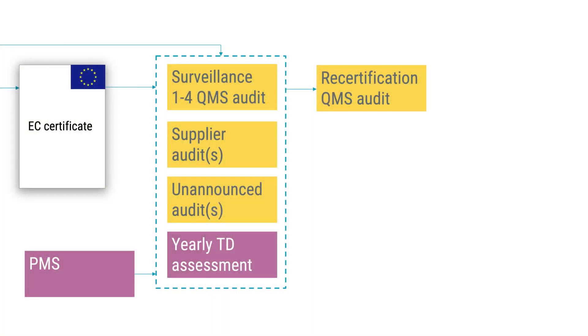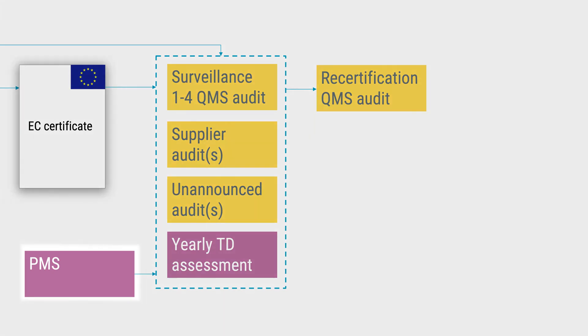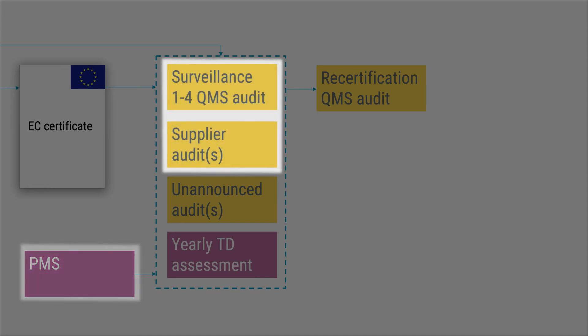When during the certification cycle the full range of the manufacturer's devices has been assessed by TD assessment and there is still time left on the certification cycle, the notified body shall focus on technical documentation relating to post-market surveillance during the remaining audits of that cycle. So when no more TD sampling is to be done, the focus will be PMS-related documentation during the coming audits.